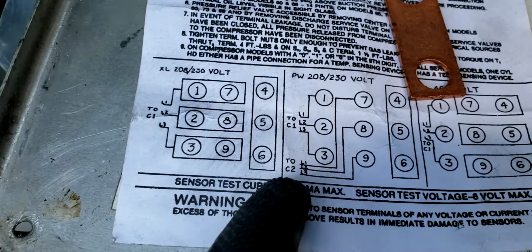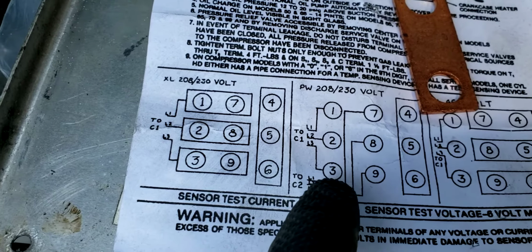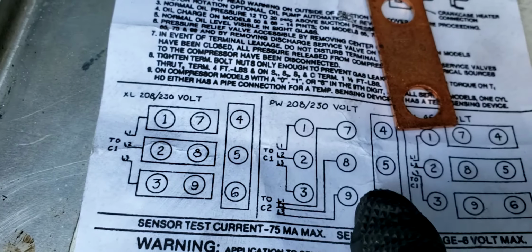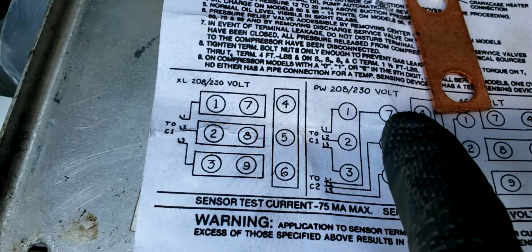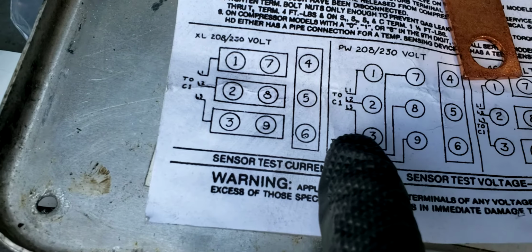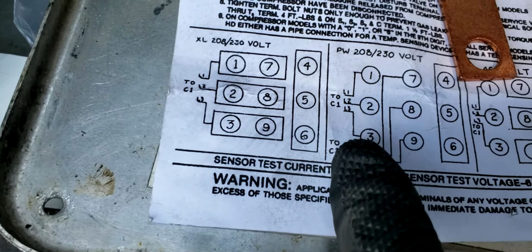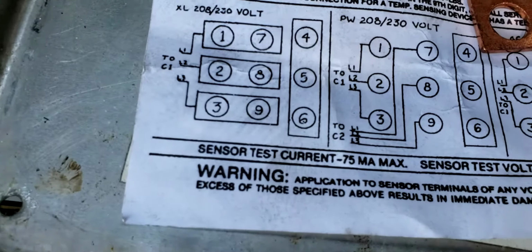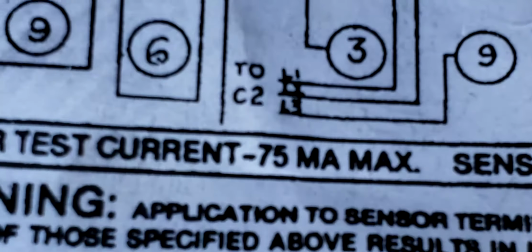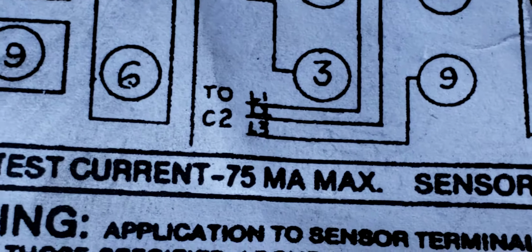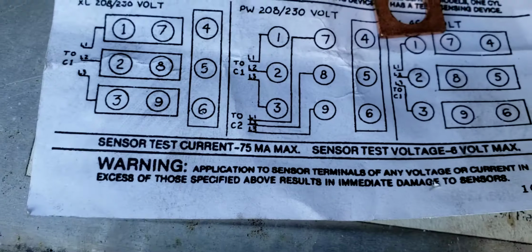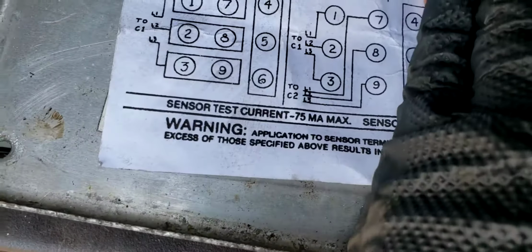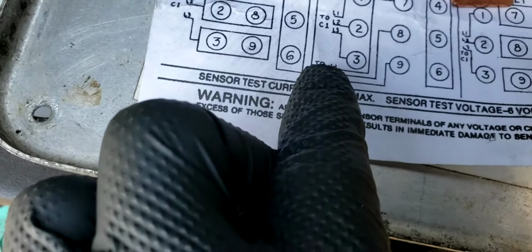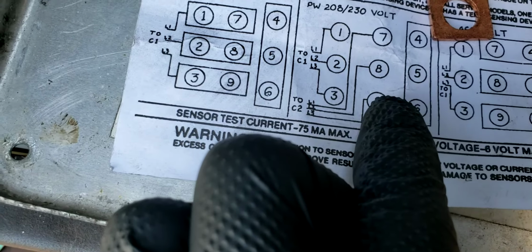So when you look at the terminals 7, 8, and 9, there you'll see that L1 will go to 7 and L2 will go to 8. Let me zoom that in some more. You can see that it's a bit right there. L1, L2, L3. Okay, so L2 will go to 5. Mistake. L2 will go to 8. L3 will go to 9.